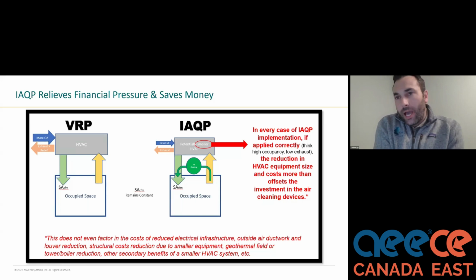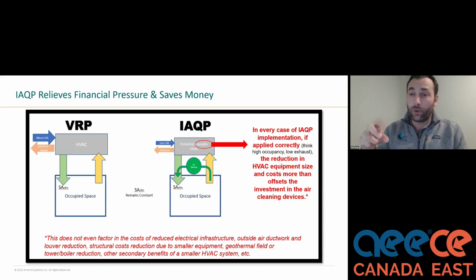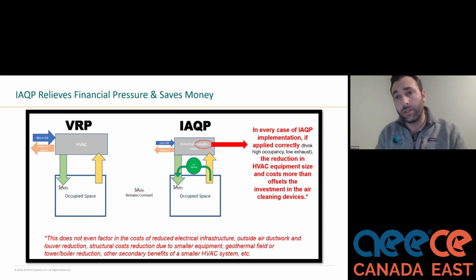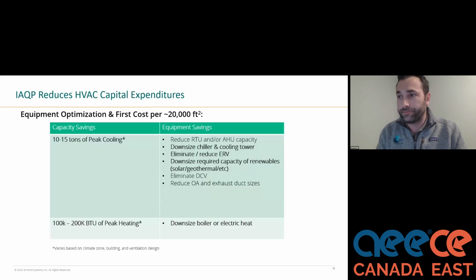In the case of using the IAQp correctly, I mentioned that we're essentially adding filtration. And many facilities folks will say, well, that means you're adding one more piece of equipment. That's going to increase cost to the design. That's not necessarily so. If you're adding filtration, you can reduce your code required amount of outside air so significantly they can end up with smaller HVAC systems by providing that air cleaning. Additionally, the filter replacements for these applications are typically far less than the costs of the energy that we are saving. So this can actually relieve financial pressure. So you can add a piece of equipment to actually reduce total cost in the project, both in terms of OpEx as well as CapEx.